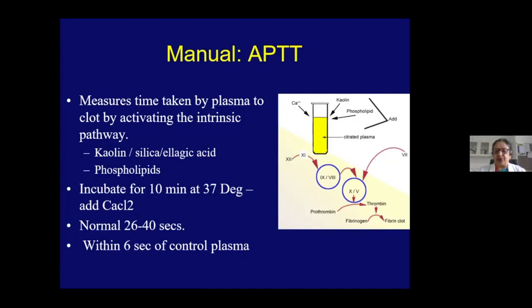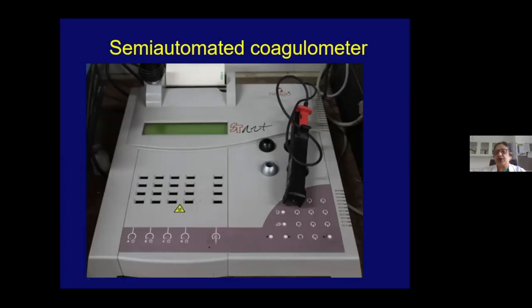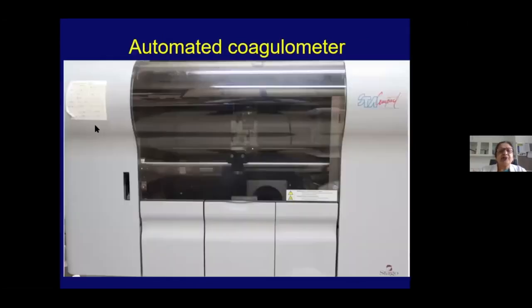Within 6 seconds of the control plasma is taken as the normal cutoff. Semi-automated coagulometers automate the detection of gel formation, giving consistent results even for untrained personnel who cannot manually detect clot formation quickly. We subsequently moved to fully automated coagulometers where everything is a closed system — you just put the sample in the tube and everything else is automated.